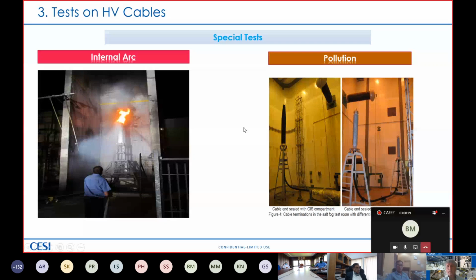Let's talk about a less dangerous special test, pollution. It's less dangerous because, of course, in this case we do not have an explosion, but for sure it's of great importance for cable termination. These are pictures taken in our Mannheim pollution test chamber. We test both HVAC up to 600 kV or HVDC up to 500 kV cable termination. In this case, you can find a loop that was also with a cable joint because it was part of a special test for a utility.